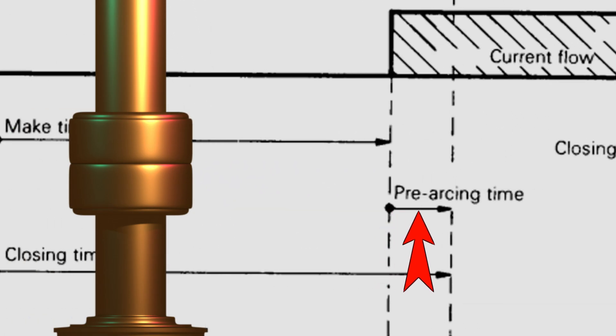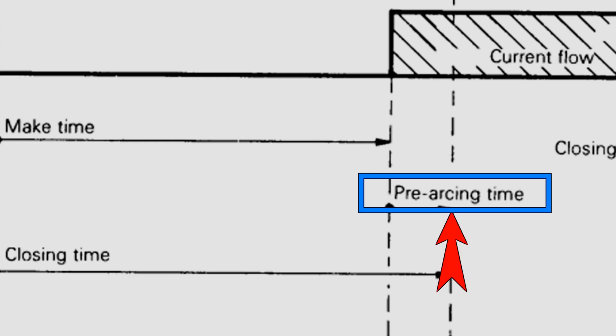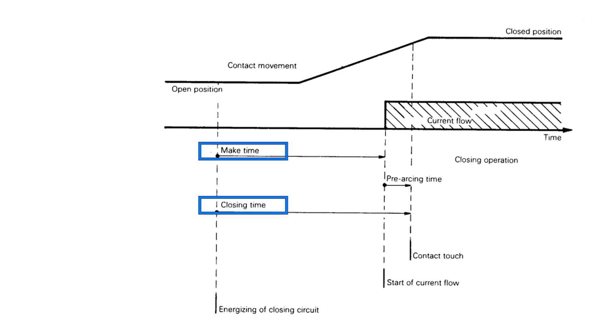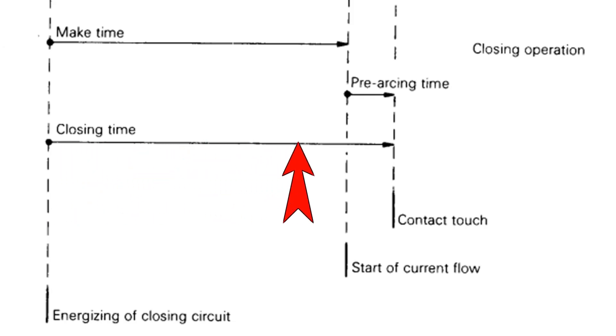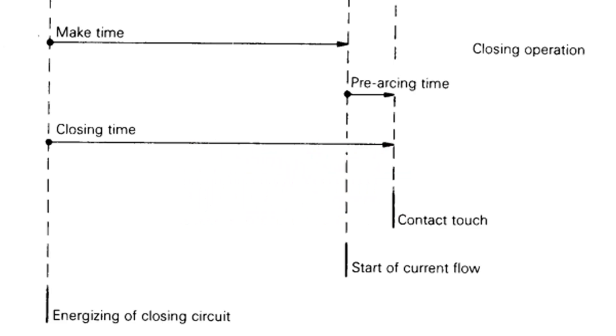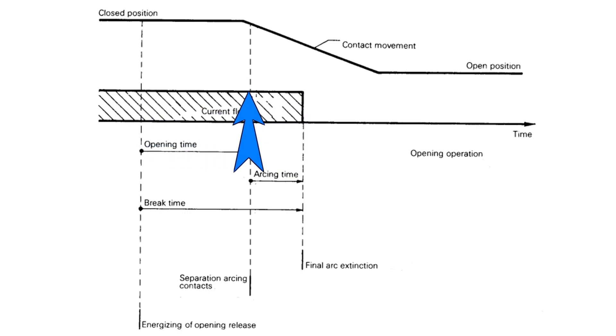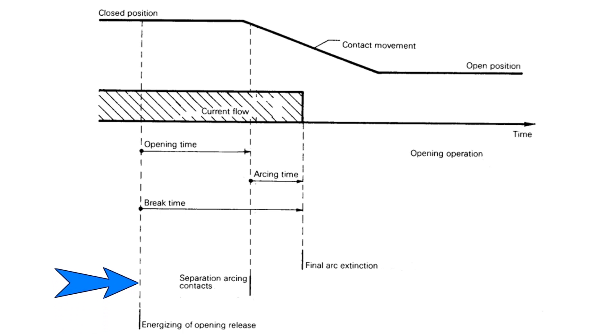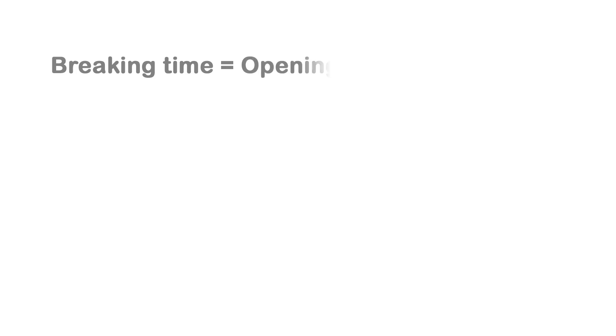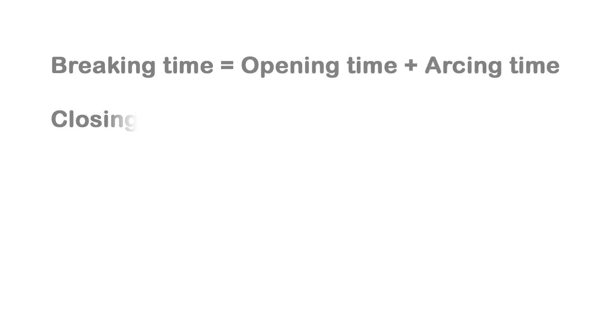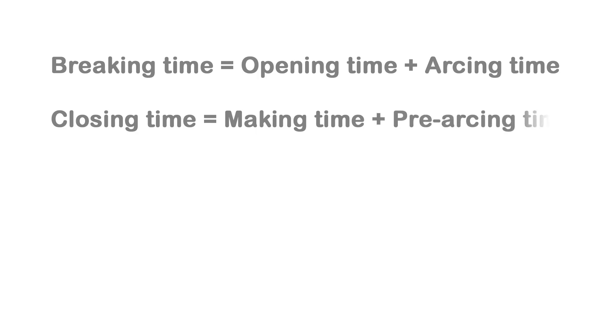The time from arc initiation to the physical contact is called the pre-arcing time. Therefore, the closing time is the sum of making time and pre-arcing time. Closing time is defined as the interval between the energization of the closing circuit and the moment the moving and fixed contacts physically touch. Breaking time is the total time taken to completely interrupt the current after the opening release trip coil is energized. So: breaking time equals opening time plus arcing time; closing time equals making time plus pre-arcing time.